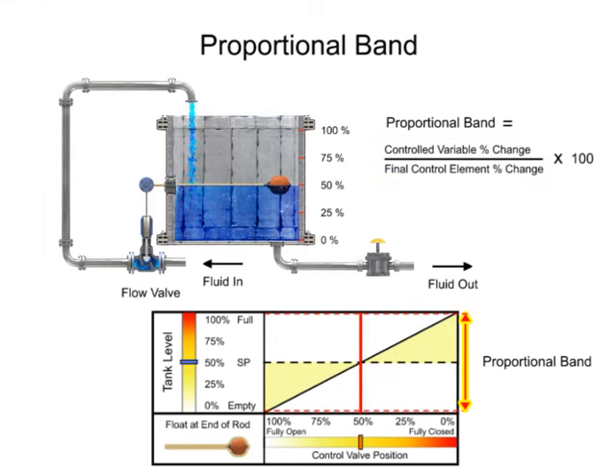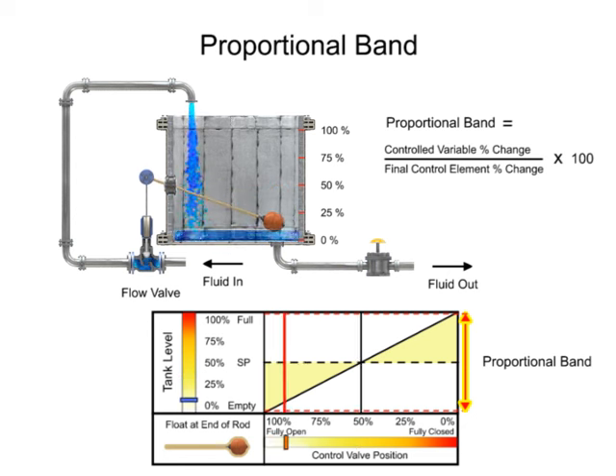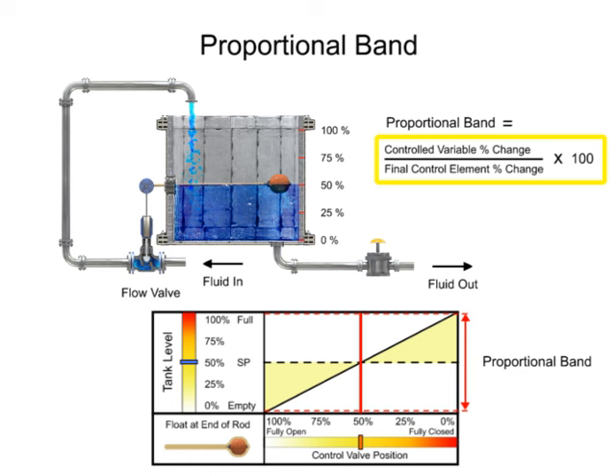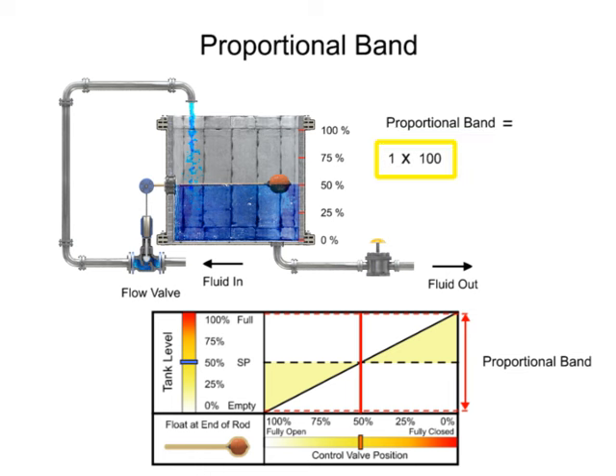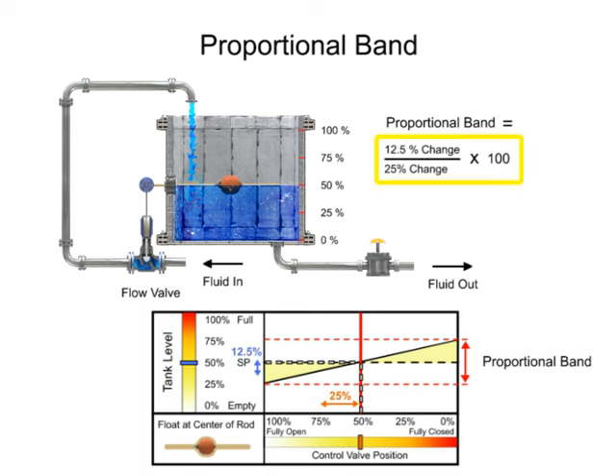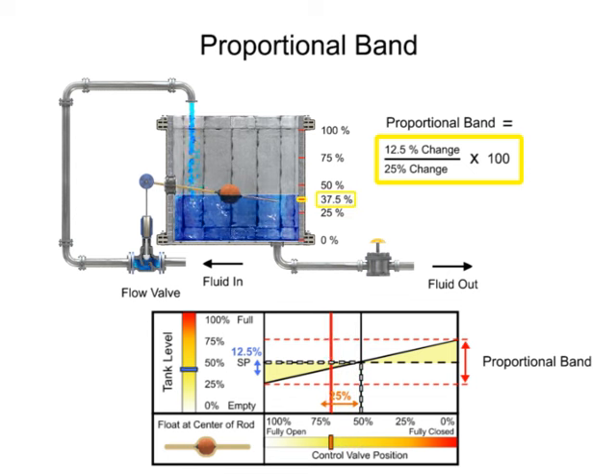The width of the proportional band determines how much of a controlled variable change is required to cause the final control element to move by a determined amount. By placing the float on the end of the rod, the fluid level has to change 100% to cause the final control element to change 100%. By placing the float at the center of the rod, the fluid level has to change 12.5% to cause the final control element to change 25%. The width of the proportional band is reduced by half.